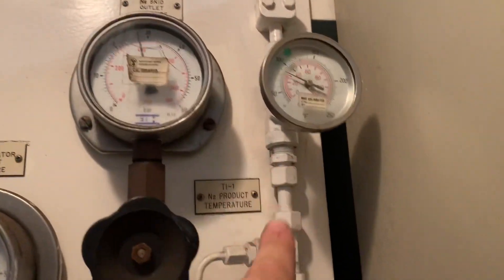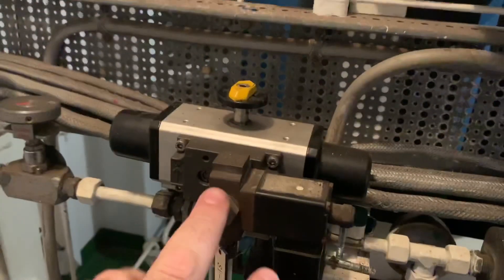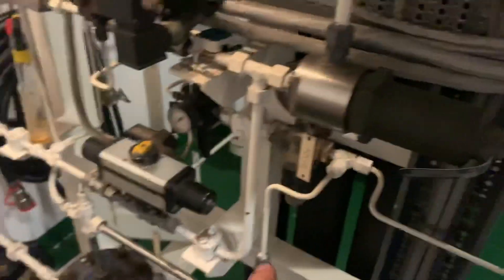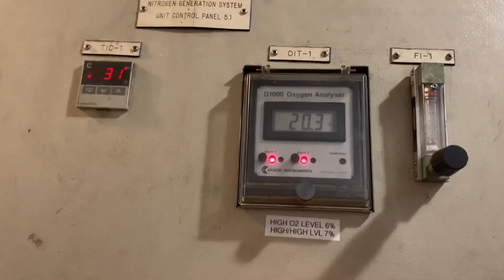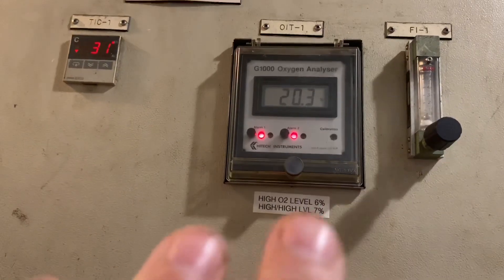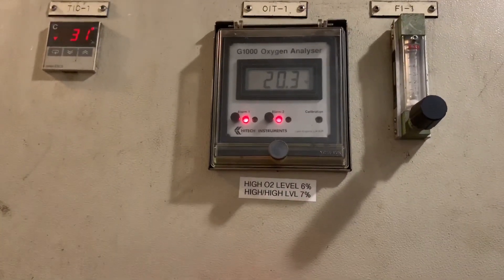Off the top here the nitrogen comes down. We've got our pressure gauge, our flow control, and this is our diverter valve — whenever it's dumping or making nitrogen, everything shuts off because it's at pressure. Then it goes out to the system. Right now it's reading 20.3% oxygen because it's off.